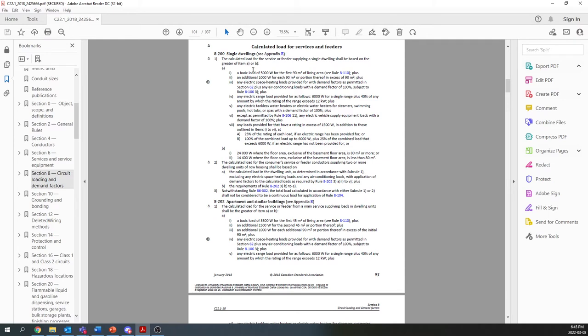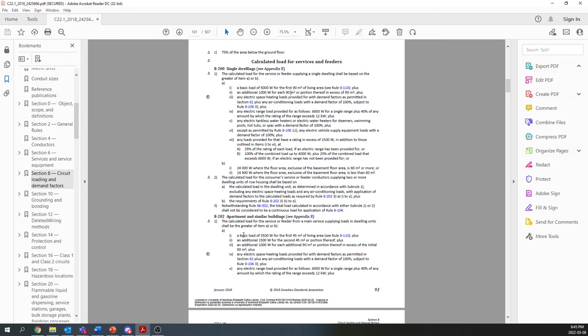It then defines kind of the calculation procedure here. And that calculated load is then used to size, if it was a new house, for example, your service size, which in Manitoba is generally either 100 amps or 200 amps. And that's the rating of your main breaker. So that's kind of an idea of how you use section 8 here.